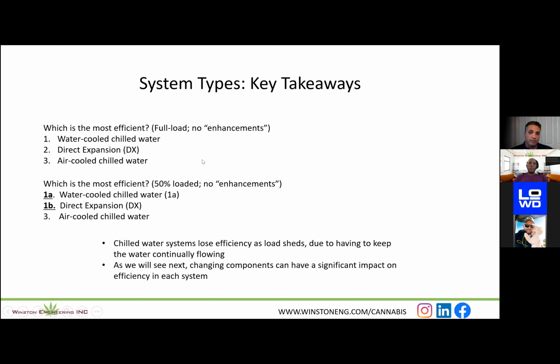Now, one thing to note here is that chill water systems are going to lose their efficiency as you shed load. So for example, just throwing some numbers out there, if you design the facility or the room for 1,000 plants to be in the room, and you only have, let's say, 500 plants in that room, that chill water still needs to keep operating and that water still needs to flow through the system. Right, so you're still going to be burning that energy, but you're going to be getting less use out of it, if you will. So in a situation where you're partially loaded, you're looking at direct expansion getting close to similar efficiencies as water-cooled chill water. And then again, air-cooled chill water just kind of pulls up the caboose in this situation as well.